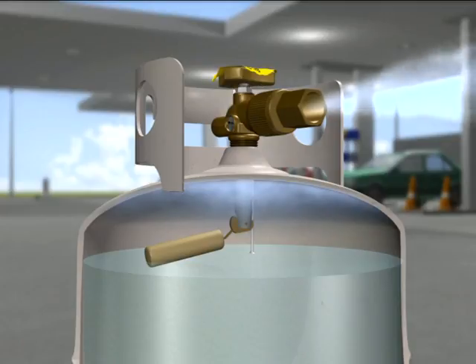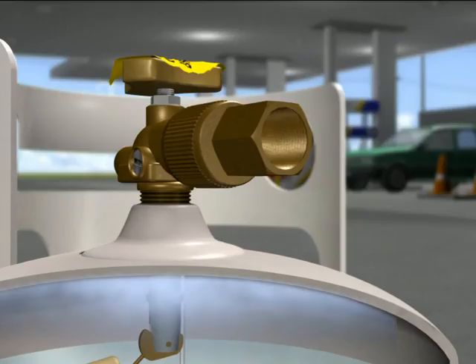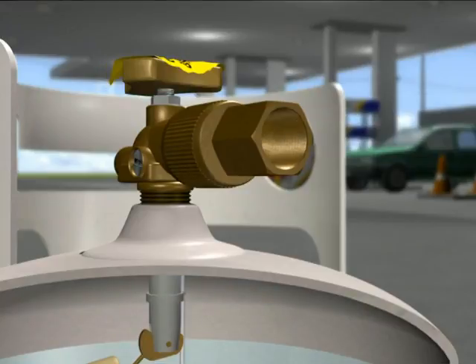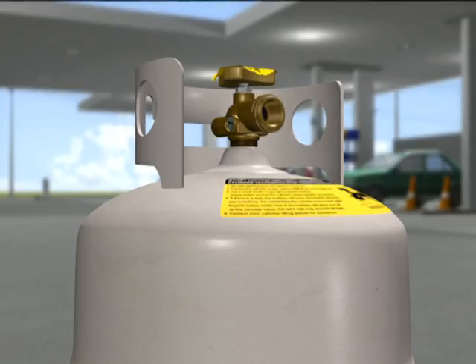Make sure you keep your filling adapter attached. Open the main cylinder valve for about five seconds and then close it. Repeat this purge three times to release all the air or nitrogen to the atmosphere.